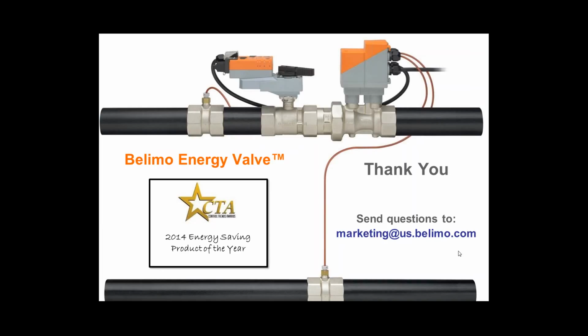David, we have one here asking, is the power output formula applicable to the system with glycol? Yes, it is. There may be some slight variations if you have water additives, and I don't know off the top of my head what they are, but they're quite similar. Even if they're scaled, what would be scaled is that 500 number. There's still a relationship between flow, delta T, and BTU, and you can't change that. Those 3 things have a relationship. If there's a skewing from the glycol, the specific gravity of the fluid, that might change that 500 number, but it isn't going to change the fact that flow and delta T are inversely proportional at fixed load.